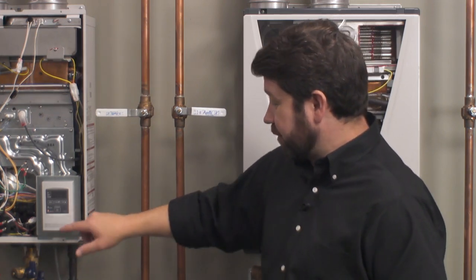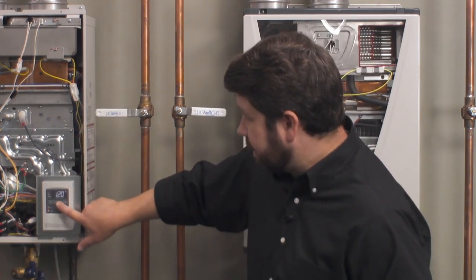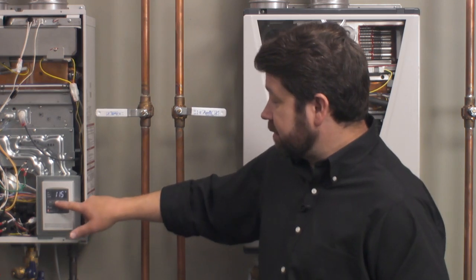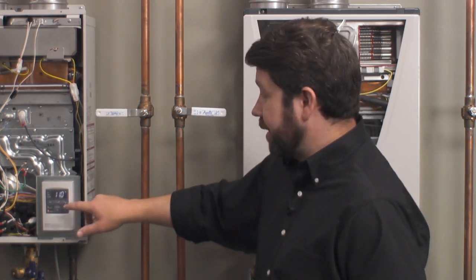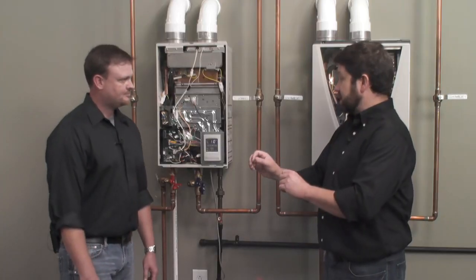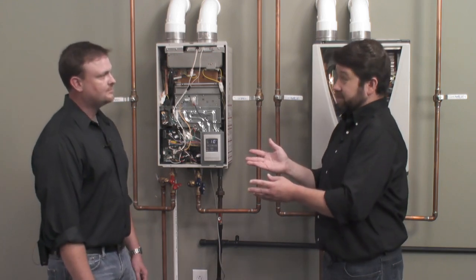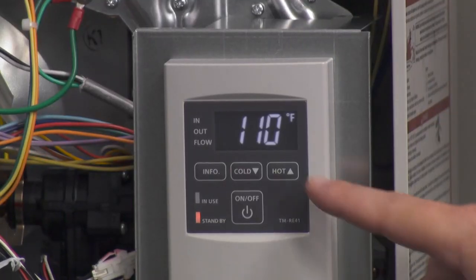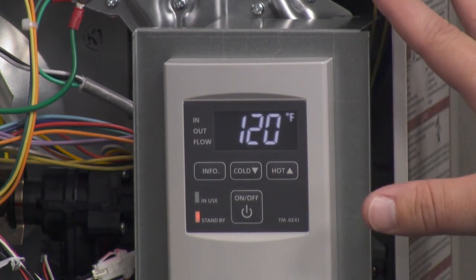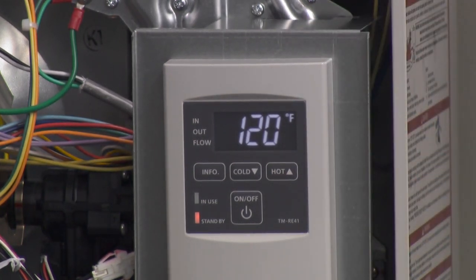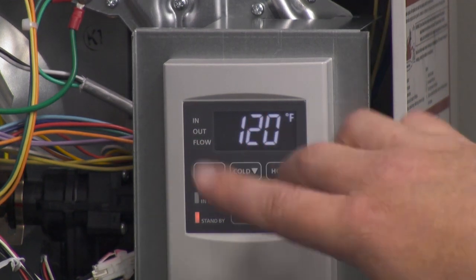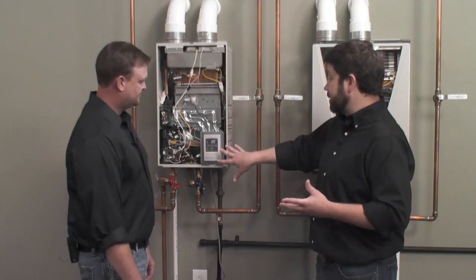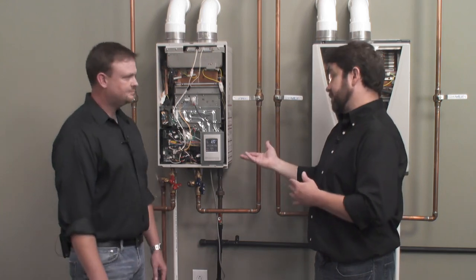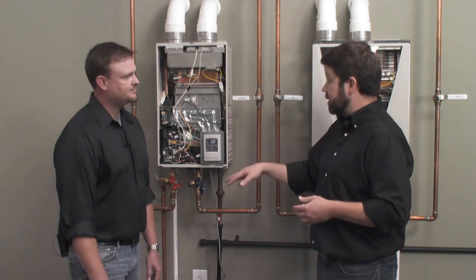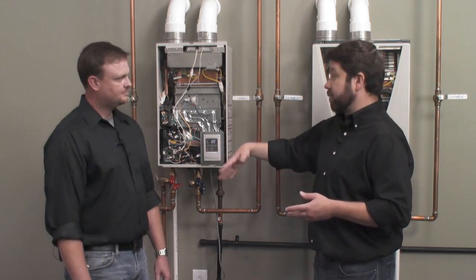What's really neat about this control, and I think we can, even with it in standby, makes it easy for me to adjust the temperature. Okay. So I don't have to get in and worry about dip switches and maybe hitting more dip switches than I need to. I've got big fingers like I do. Now this one is capped at 120. If we need temperatures above 120, there is a method that we can do to override that. So we know that not everything is one-size-fits-all if you need sanitary for a dishwasher or something like that. But 120 is where it comes from the factory, and that's what we'd recommend.